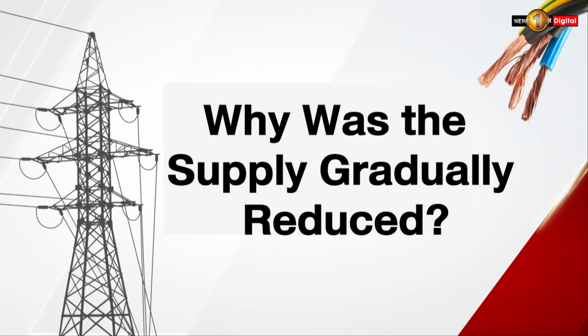Why was the supply gradually reduced? Yesterday was a Sunday, and we often refer to this as the sunny Sunday effect. On Sundays, there is typically no commercial load, resulting in a significantly reduced system load. Additionally, with ample sunlight, solar power plants operate efficiently, further lowering the system demand. This creates a situation where the system's stability is compromised, leading to incidents like the one we experienced.